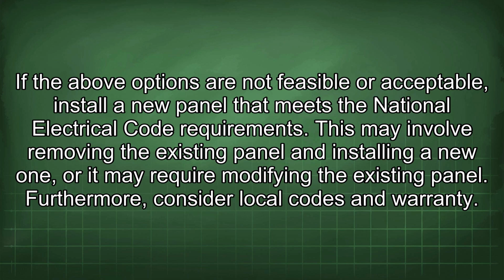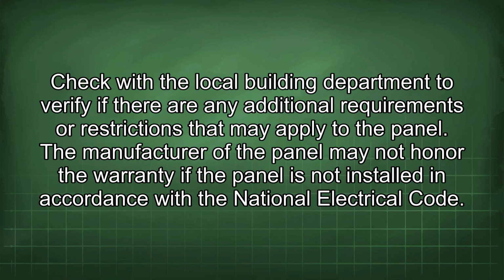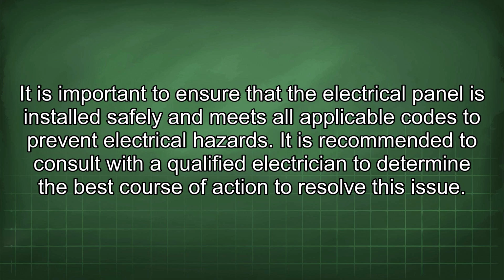Furthermore, consider local codes and warranty. Check with the local building department to verify if there are any additional requirements or restrictions that may apply to the panel. The manufacturer of the panel may not honor the warranty if the panel is not installed in accordance with the National Electrical Code. It is important to ensure that the electrical panel is installed safely and meets all applicable codes to prevent electrical hazards. It is recommended to consult with a qualified electrician to determine the best course of action to resolve this issue.